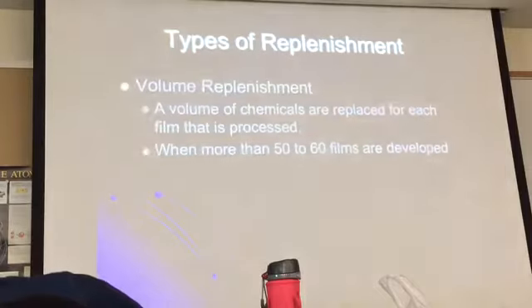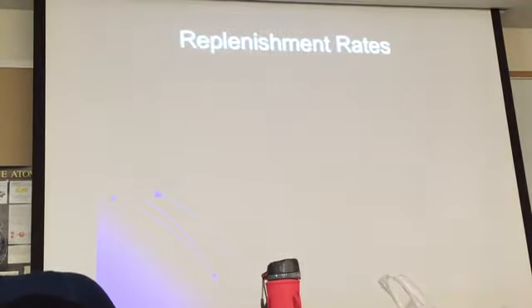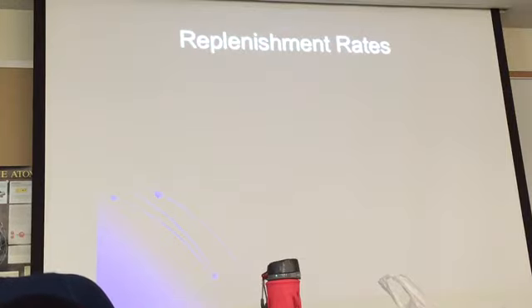Volume replenishment — chemicals are replaced for each film that is processed. This is more convenient for high-volume facilities. When you work at a decent-sized hospital, this is what you want. A high-volume place like Kaiser, going 24/7, would need volume replenishment. For every inch of film, you add four to five milliliters of developer and six to eight milliliters of fixer.